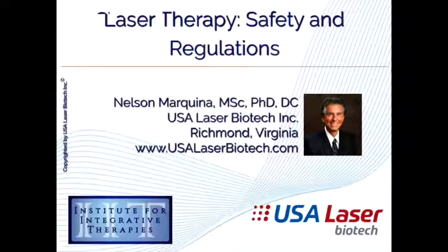What it means is it fans out enough, so the intensity went down, so it doesn't cause damage. It's all based on the intensity. And more powerful lasers, of course, have a longer DNRO. So we have to watch that one. For example, a 980 nanometer laser with 15 watt power, the DNRO is probably about 3 meters or so, about 9 or 10 feet. At that level the concentration is high, even though the distance is longer. So we have to be careful on that.